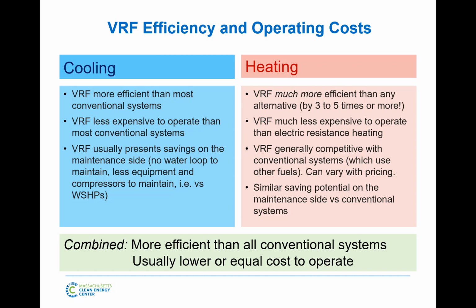And again, similar savings potential on the maintenance side of VRF. On the heating side, there's no hot water to maintain. Overall, your air source heat pump is going to be more efficient and usually cheaper to operate, despite our current prices here. Up in Ontario and Canada, our ratio of gas to electricity is often worse. Worse meaning gas is even cheaper and electricity is more expensive than here, and air source heat pumps are still very, very popular despite it being even colder.